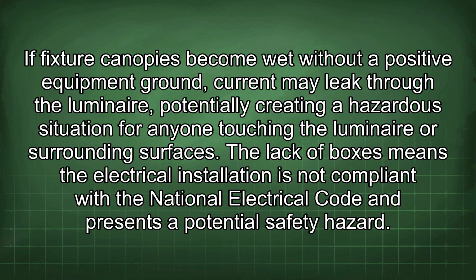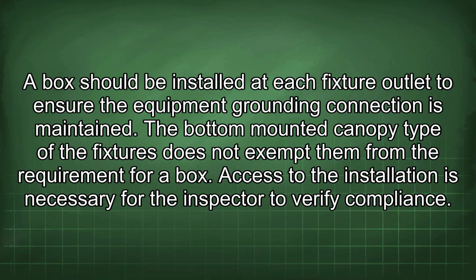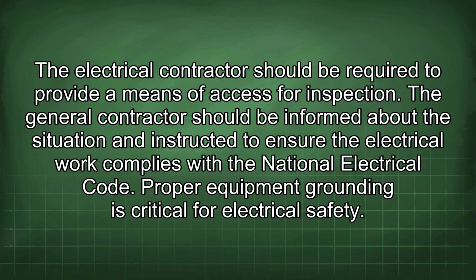The lack of boxes means the electrical installation is not compliant with the National Electrical Code and presents a potential safety hazard. A box should be installed at each fixture outlet to ensure the equipment grounding connection is maintained. The bottom-mounted canopy type of the fixtures does not exempt them from the requirement for a box. Access to the installation is necessary for the inspector to verify compliance. The electrical contractor should be required to provide a means of access for inspection.